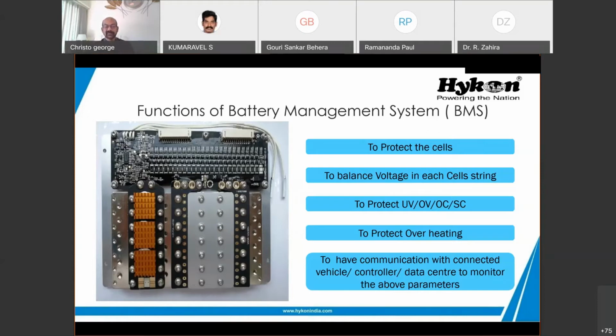There are sensors inside the BMS or in each battery. Depending on the size of the battery, there are heating and temperature sensors that check whether the cell voltage or string voltage is going up. If it goes up, at set parameters like 50 or 80 degrees, it can switch off the cells from the external device or connected load. So it has protection against heating.